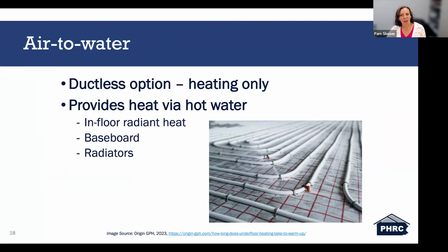It's a ductless option. And it's important to note it provides heating only, not cooling. So unlike traditional air-based systems that use forced air, this system heats water, which is then distributed through the home for comfort. That water can be distributed through in-floor radiant heat systems. It could be baseboard heating units or traditional radiators that you find in older homes as well. These systems are ideal for homes that already may have baseboard heaters, the hydronic heating infrastructure, as we call it, or radiators. It could be a good solution to switch over. But like I stated before, the biggest downfall is that it is heating only, and there's no cooling that goes along with it.